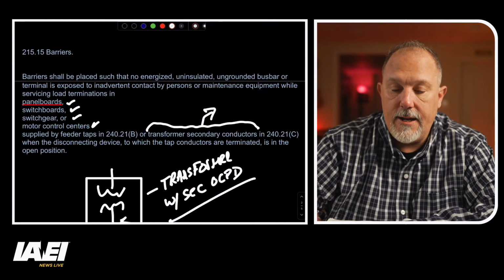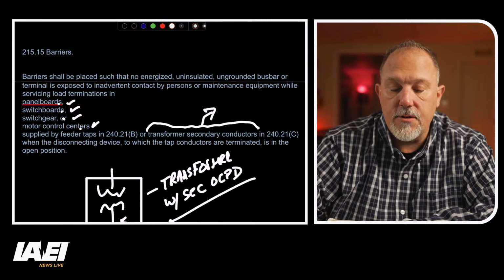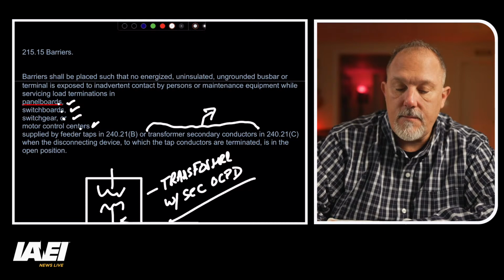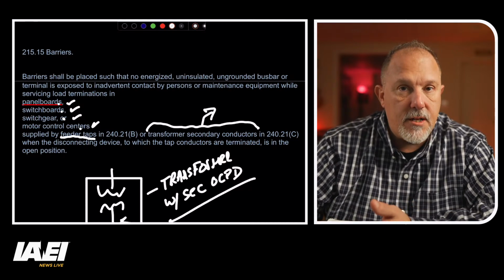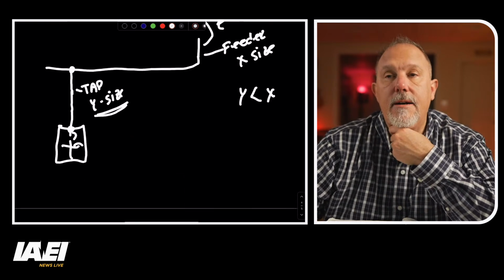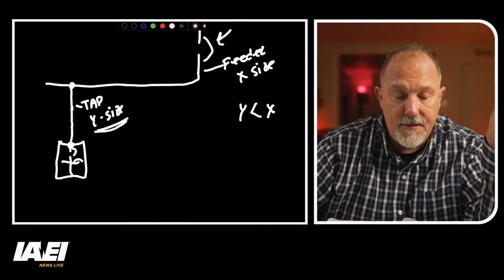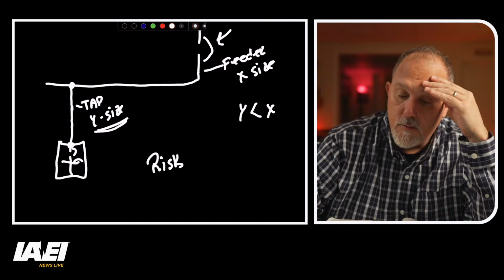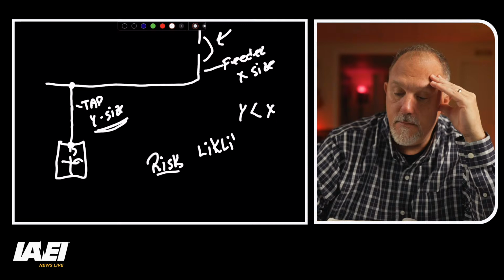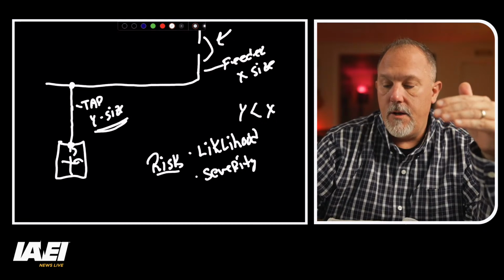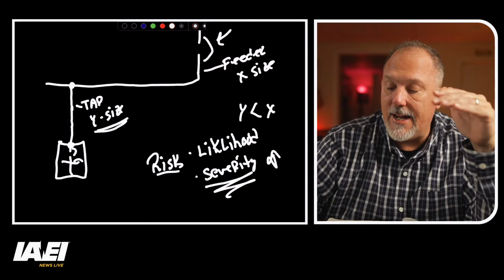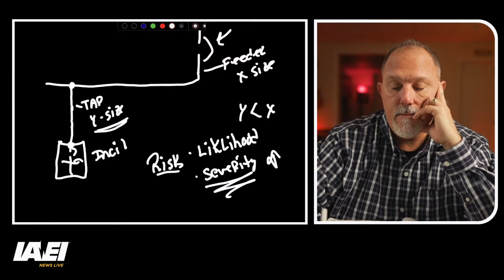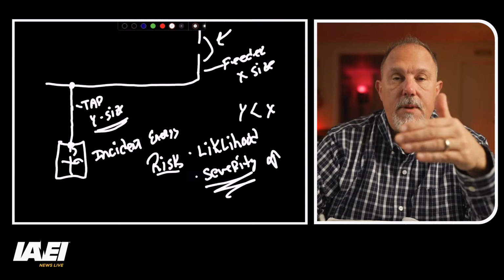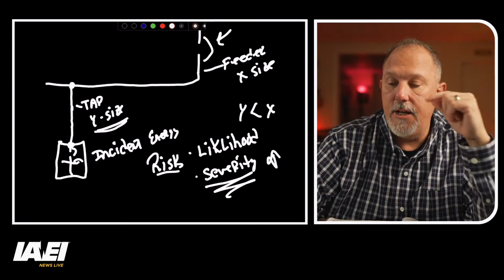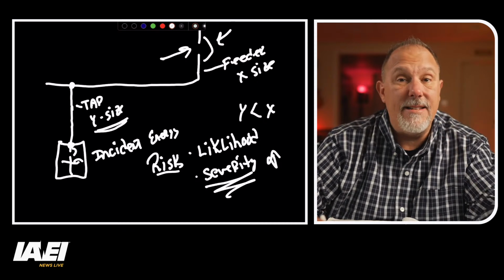I would go back to the list. Anywhere where you have a panel board, switchboard, switchgear, or motor control center supplied by feeder taps, or transformer secondary conductors. We just talked about transformer secondary conductors. Now we're talking feeder taps. And the reason is I have risk. Risk is comprised of likelihood and severity. So in this case, my severity is high because incident energy is going to be higher here because the protecting overcurrent device, which is this feeder, is inflated in size.